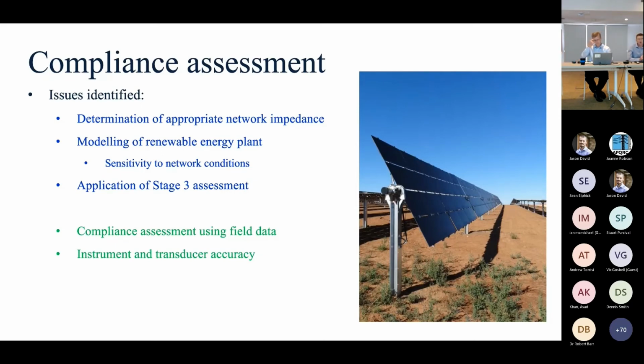From the post-connection compliance assessment area, two issues were identified. One is how we go about actually assessing compliance using field measurements. We've talked a little bit about how emissions are given as a voltage, but we're generally measuring currents. The standard also requires us to try and evaluate plants in isolation, i.e. with a sinusoidal supply voltage waveform. We know that's not what happens when we go and measure field data, and there is no prescriptive way to really assess compliance based on field data at the moment. And then there are the issues around instrument and transducer accuracy, which again we've touched on this morning already.